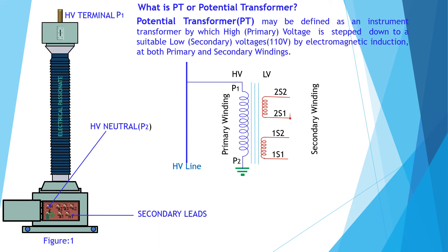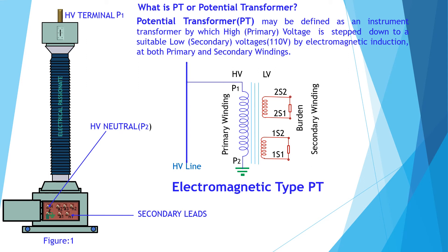This is the burden. Voltmeter and wattmeter are the measuring instruments, and relays connected across the secondary are called its burden. Potential transformers do not differ much from power transformers, except the load or burden is very small — a few volt-amperes.